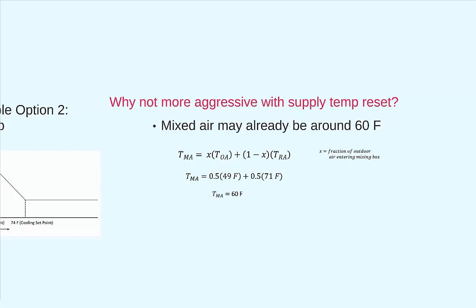The second reason we don't want to bring supply temperature set point much above 60 is for wasted fan energy. If we did have spaces in cooling, an increase in supply air temperature may result in the dampers opening more, which would require the fan to speed up more and consume more energy. And the final reason we don't want to get too aggressive with the supply air temperature reset schedule requires that we do a little case study.